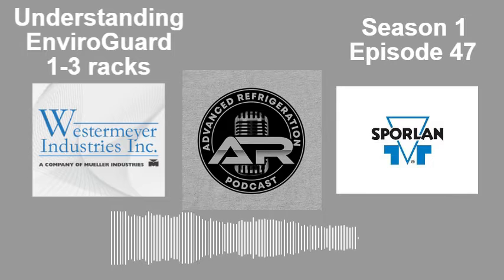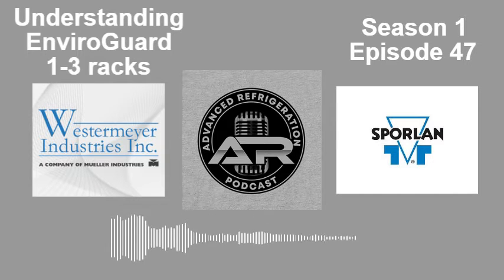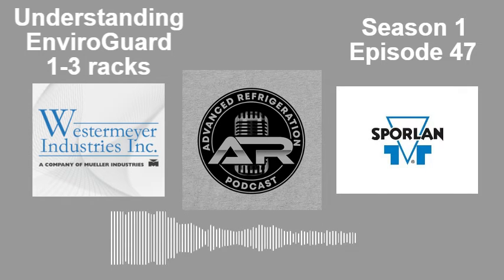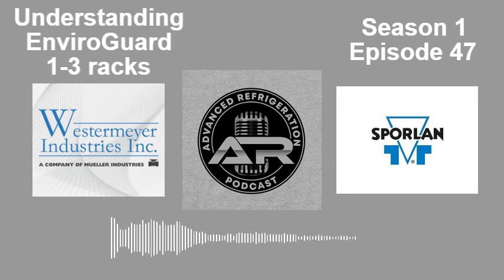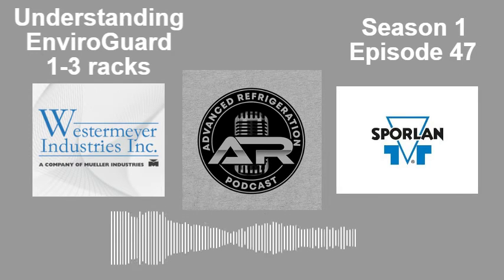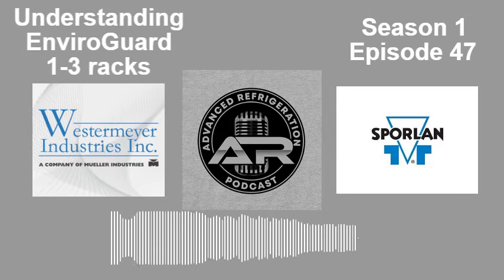The biggest thing is a lot of these Enviro-Guards, especially 1 and 2, you'll find them locked off. You'll walk up to them and these guys say they don't work. They have the SPR tank valved off and they're running like a critically charged rack. When you run it like a critically charged rack, the biggest issue is now you have nowhere for that refrigerant to go. So now you may put 25 extra pounds of gas in there and you're having head pressure issues now. And you're burning through tons of energy because you now have the tank valved off and you're just running it as a clear sight glass. So you may lose 25, 30 pounds and you're getting a call for a case running warm.